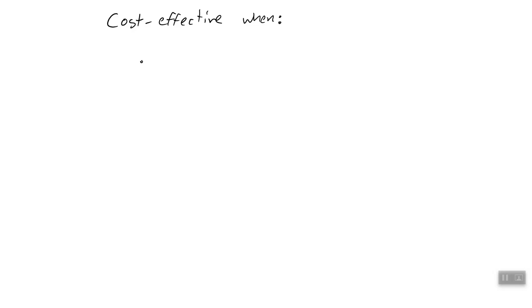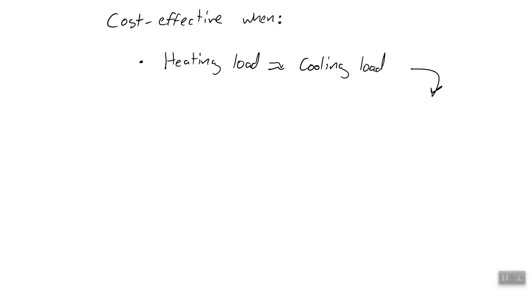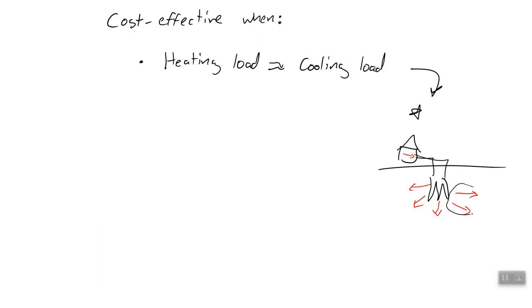You should really consider it's very cost effective to do a ground source heat pump when, this is probably the most important, your heating load is approximately equal to your cooling load. The reason for that is, if you have a building and it is rejecting heat to the ground, that would be in cooling mode, right? It's taking heat from the building and putting it into the ground. Let's say your house is in Florida, where you require a lot of cooling and then almost no heating. What this means is that over time, the only thing you're doing is adding heat to the ground, and so the temperature of your ground will go up in the summertime.